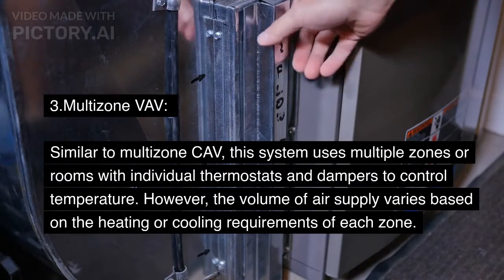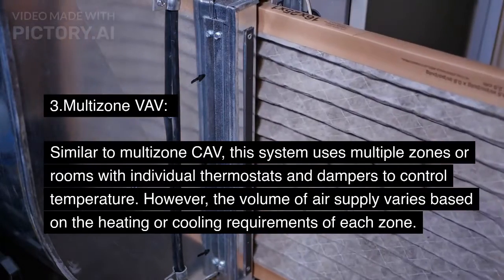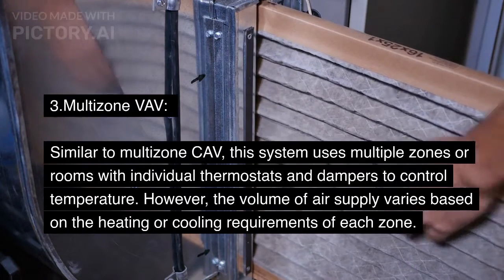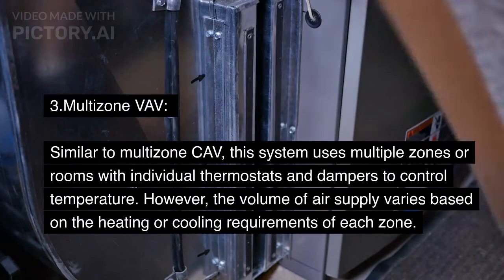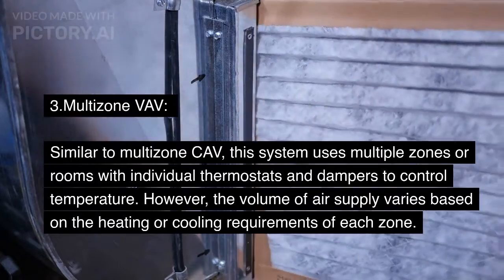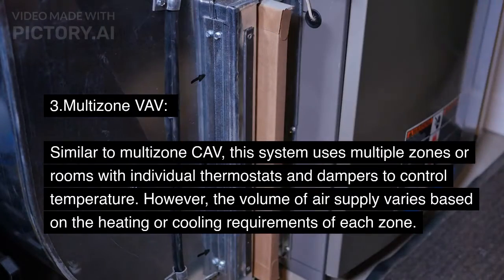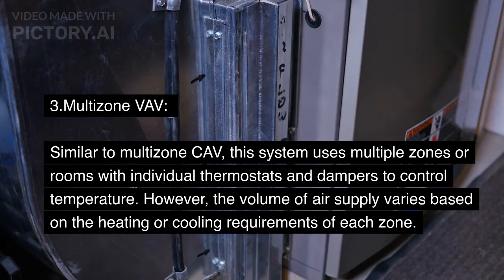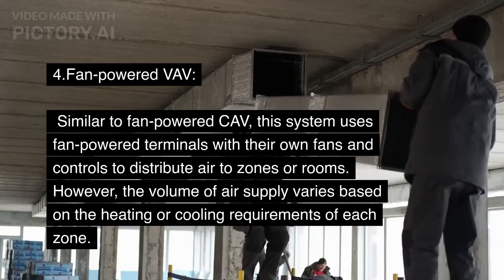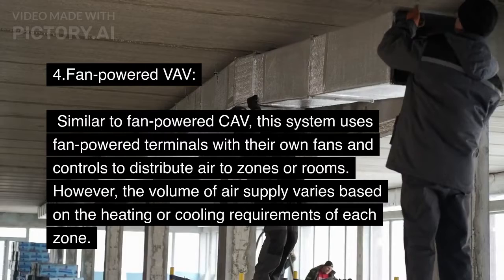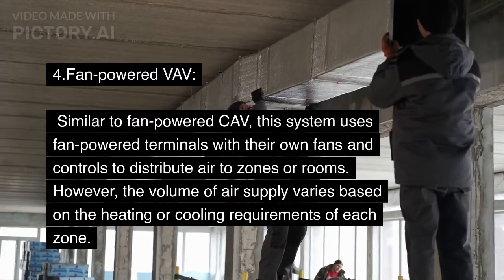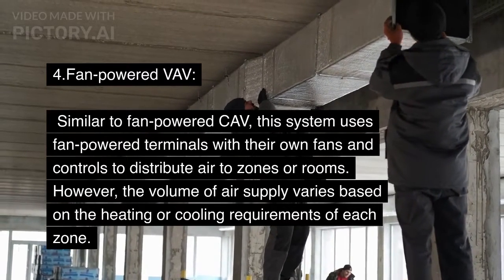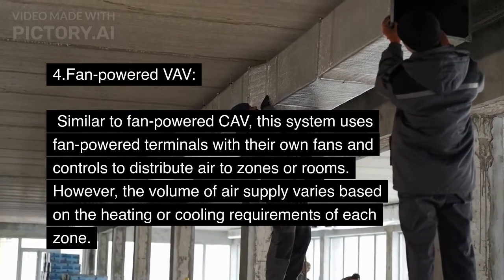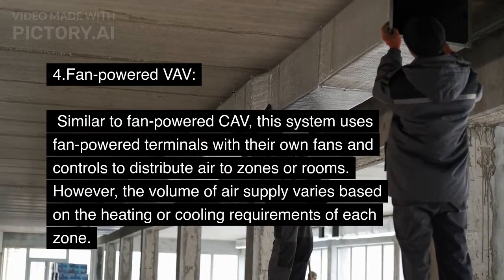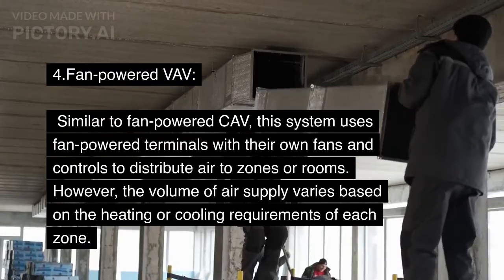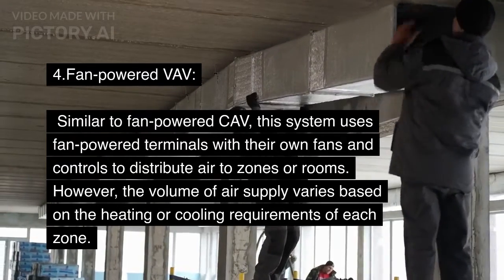3. Multizone VAV. Similar to multizone CAV, this system uses multiple zones or rooms with individual thermostats and dampers to control temperature. However, the volume of air supply varies based on the heating or cooling requirements of each zone. 4. Fan-powered VAV. Similar to fan-powered CAV, this system uses fan-powered terminals with their own fans and controls to distribute air to zones or rooms. However, the volume of air supply varies based on the heating or cooling requirements of each zone.